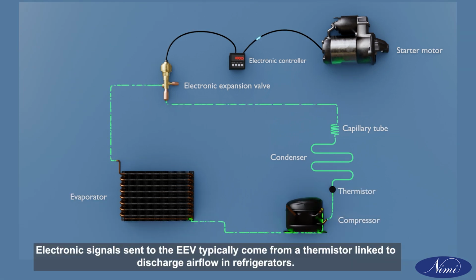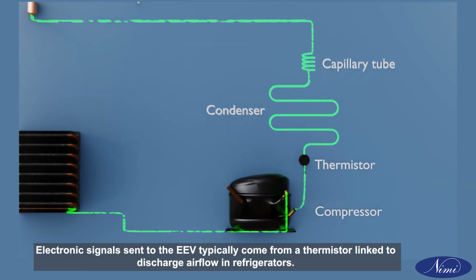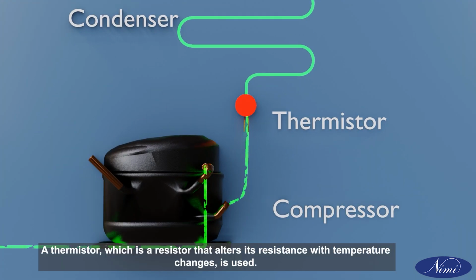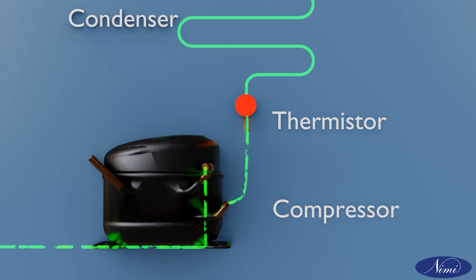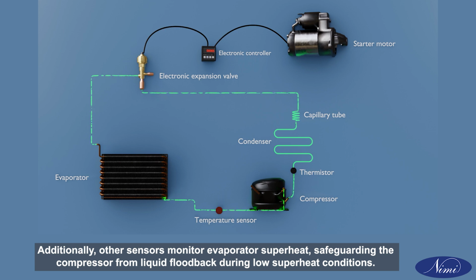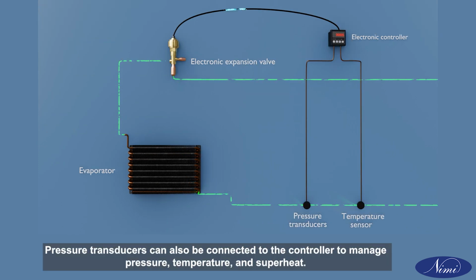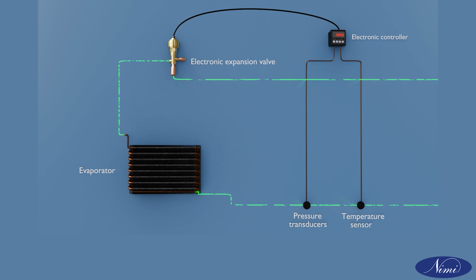Electronic signals sent to the EEV typically come from a thermistor linked to discharge airflow in refrigerators. A thermistor, which is a resistor that alters its resistance with temperature changes, is used. Additionally, other sensors monitor evaporator superheat, safeguarding the compressor from liquid floodback during low superheat conditions. Pressure transducers can also be connected to the controller to manage pressure, temperature, and superheat.